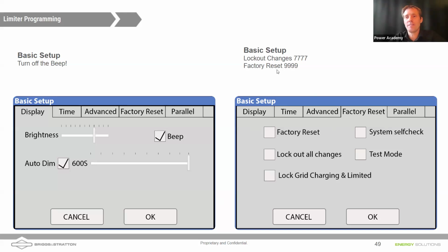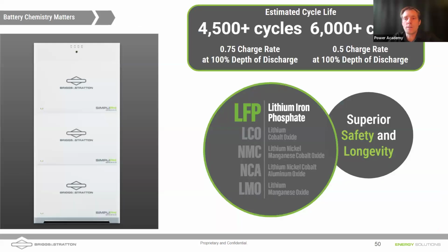It's 9999, right? If you want to lock out changes, so you're doing an installation, you're doing all the setup, you want to make sure the homeowner doesn't mess with the settings that you put in there. You can go in and check the box for lockout all changes, click OK. It'll ask you for a password. You type that 7777, it'll lock the screen. Until you uncheck the box, the changes will not be able to be made on the settings.